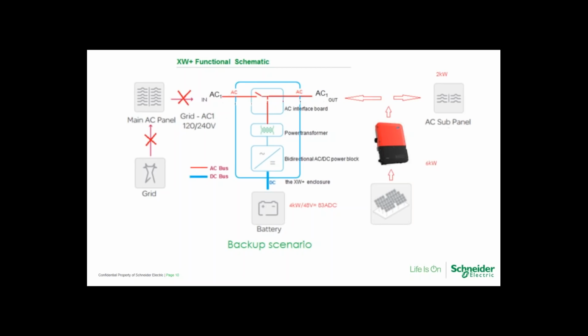And then once it reaches the bulk voltage, the XW or the Conext SW, for that matter, the AC coupling feature will shift the frequency up. And that is designed to curtail the grid tie inverter if that grid tie inverter has curtailment capability, or if it's a standard UL 1741, then it'll shut down and it'll count down for 5 minutes and then it'll reconnect. So if it does have curtailment or an off-grid mode, then it will throttle down the output commensurate with the load, and then it will also provide a 3-stage charging in that mode. So that's really a great feature to have.